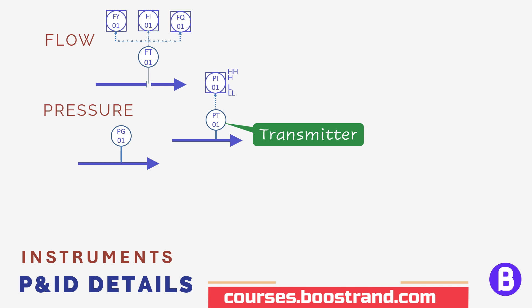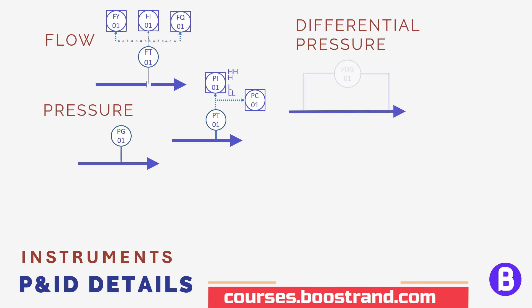We can also use a differential pressure gauge, which can be used to measure the difference between the pressures at two points. They are commonly used to measure the pressure drop across a certain component, whether it's equipment or instrument, or even a fitting such as the strainers of a pump.